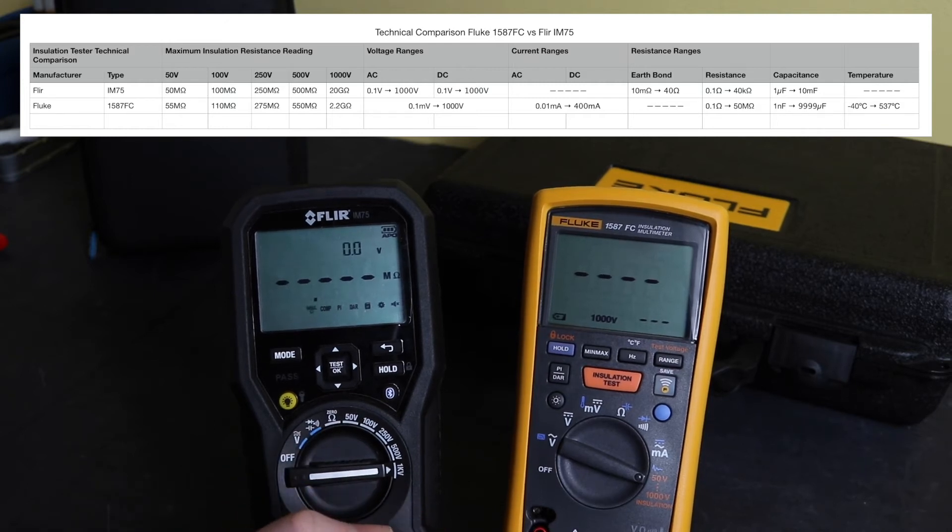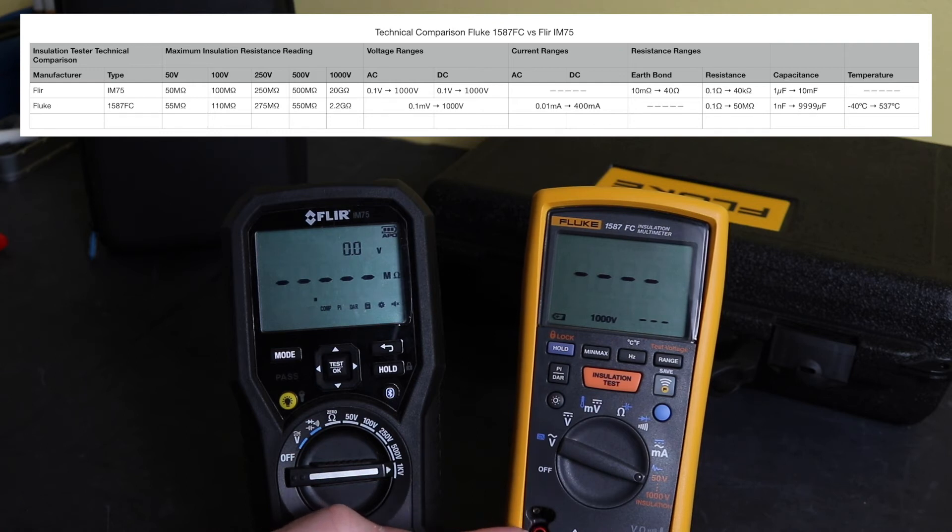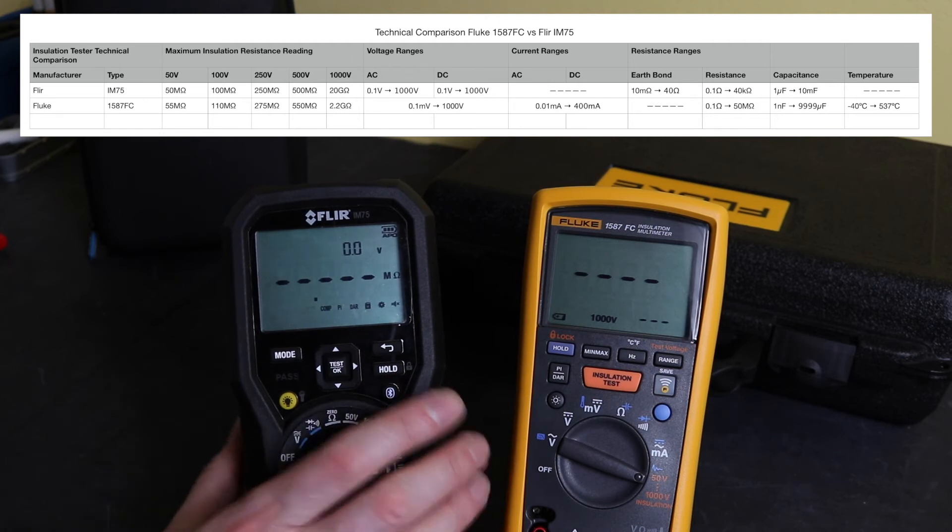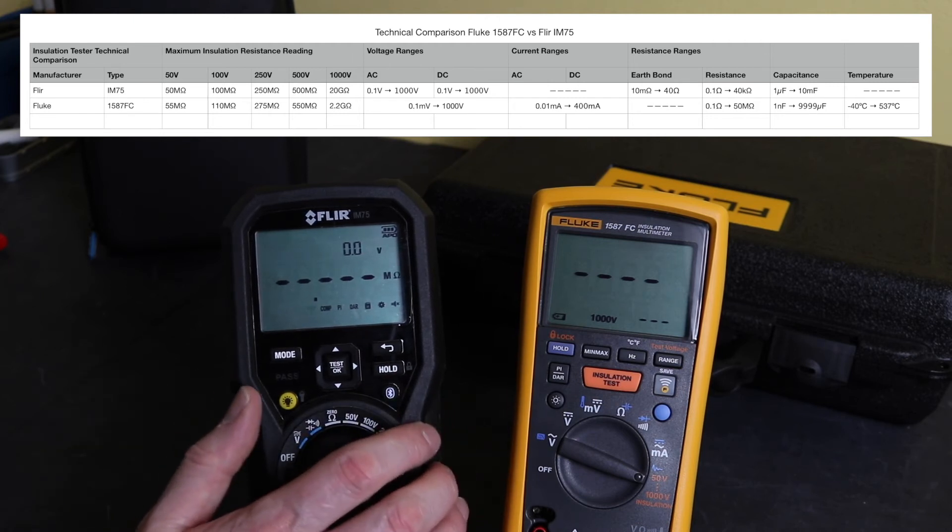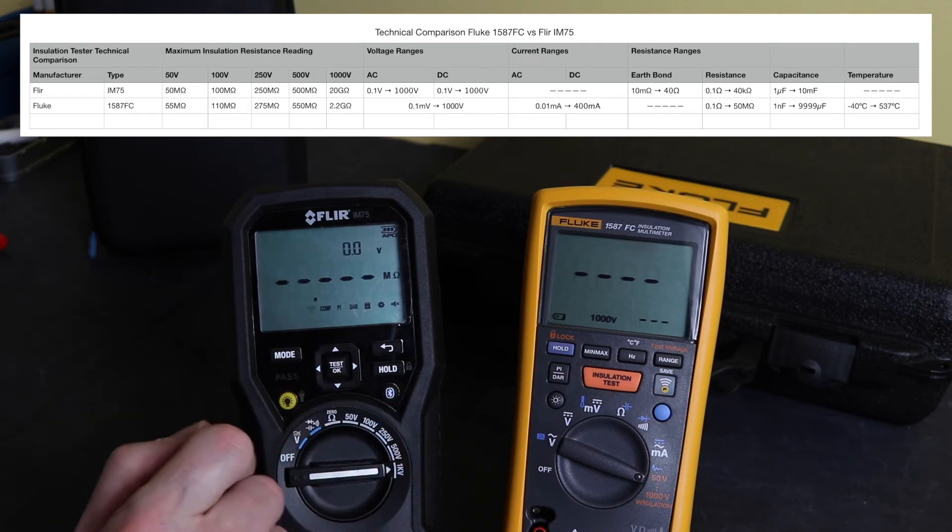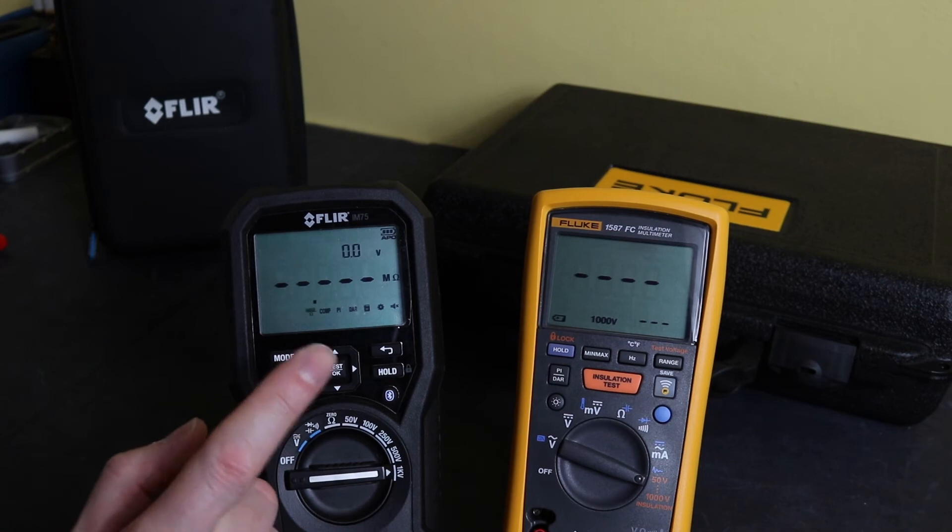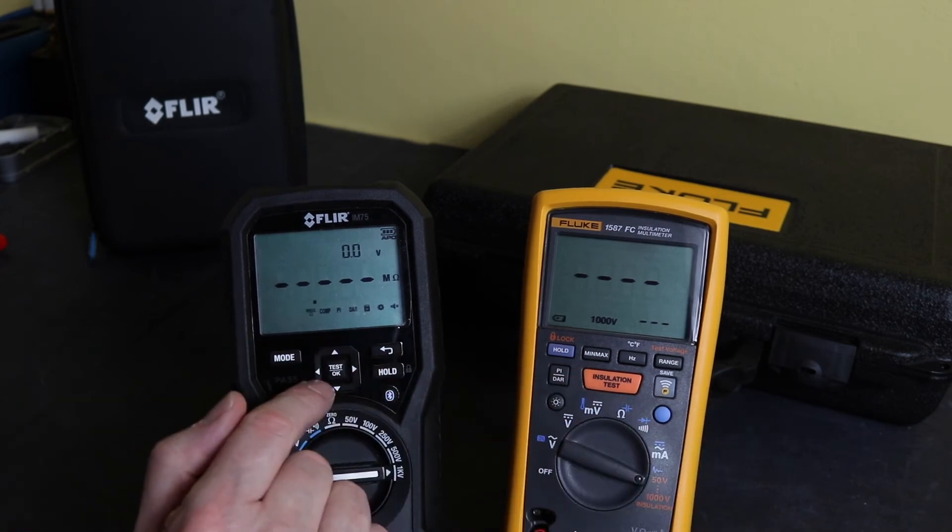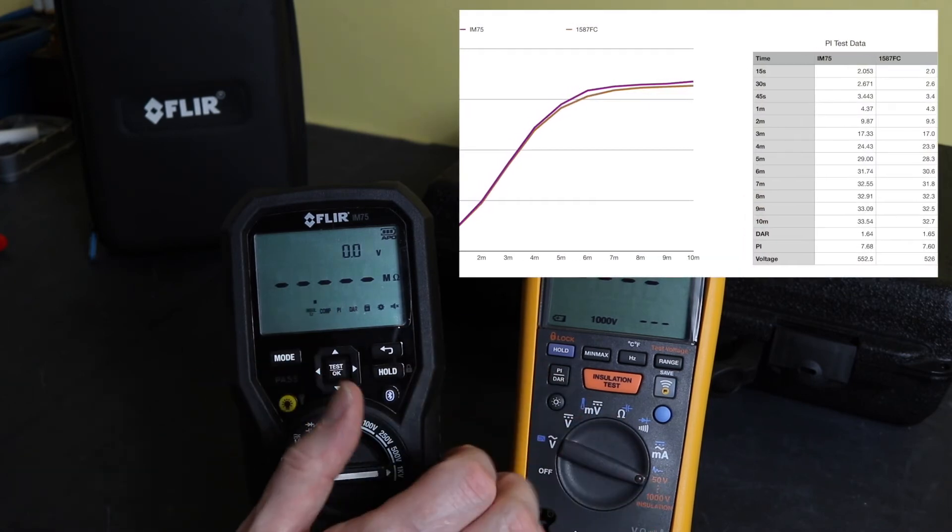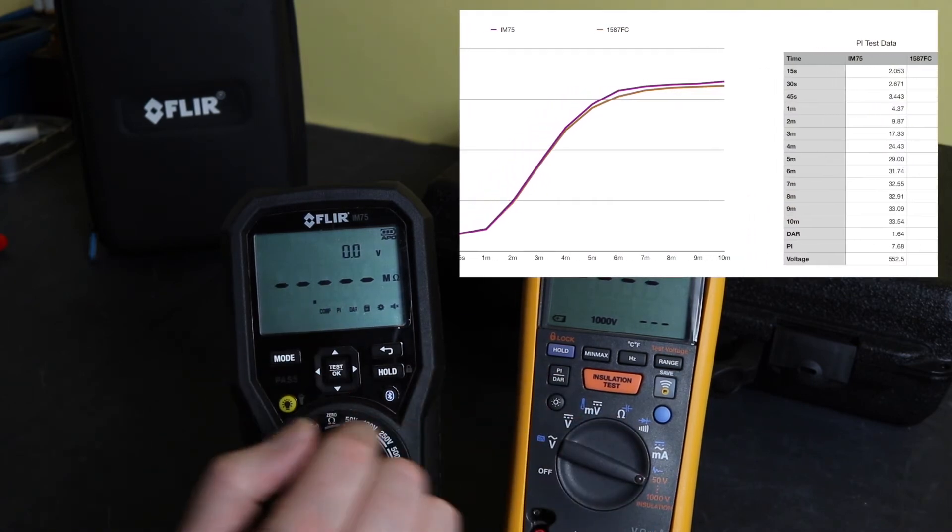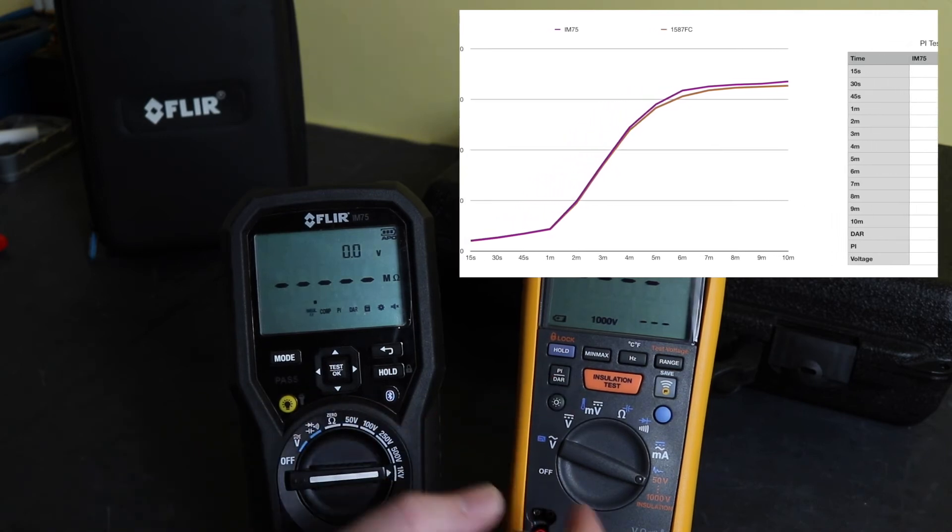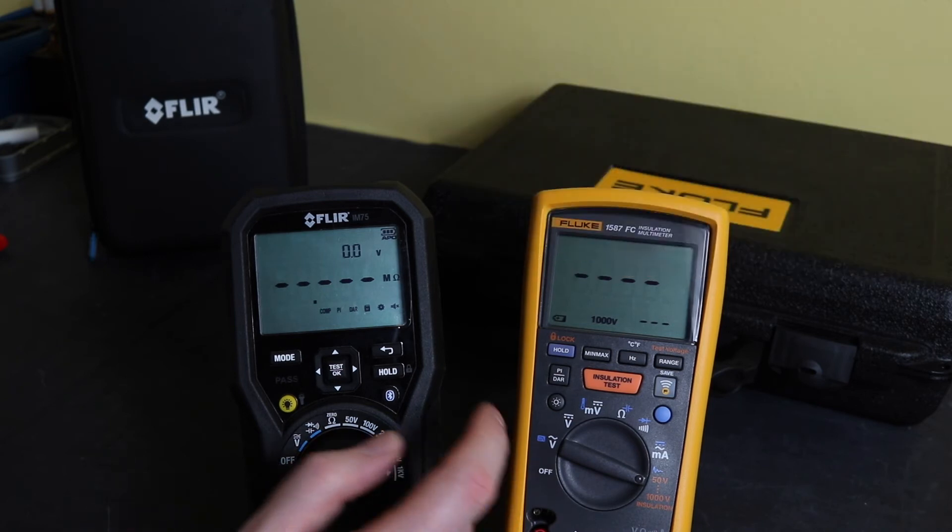But they're all the same, they've got 50, 100, 250, 500, and 1000 volts, exactly the same on the instrument. For the Flir, 50, 100, 250, 500, and 1kV. Range-wise on the Fluke here, at 1000 volts you can go up to 2.2 gigaohms, and at 500 volts that drops then down to 550 megaohms. On the Flir at 1000 volts you can actually get up to 20 gigaohms reading, and that drops down to 500 megaohms at a 500 volt test voltage. In terms of functionality for the insulation test, you have DAR and PI on both instruments that can be selected using the menu buttons up here, so totally comparable to one another with that functionality.